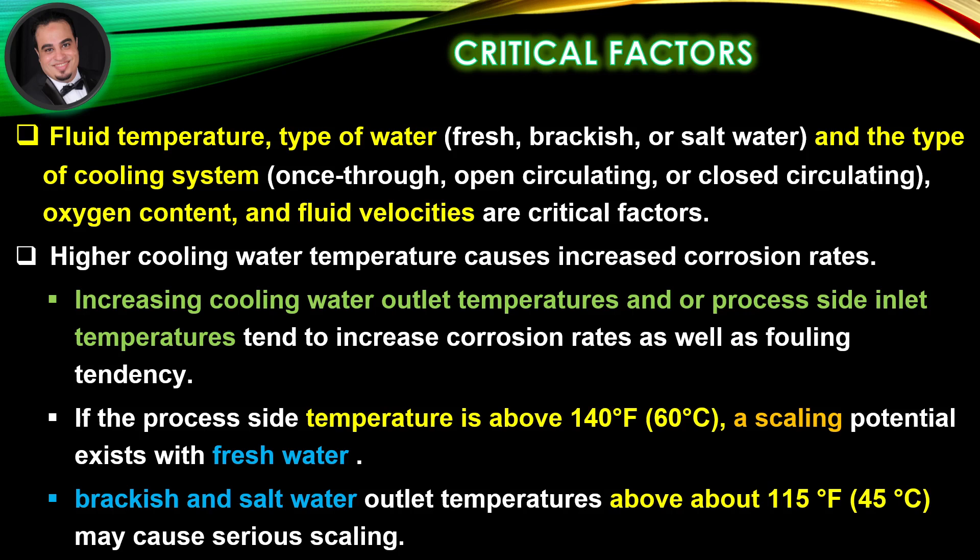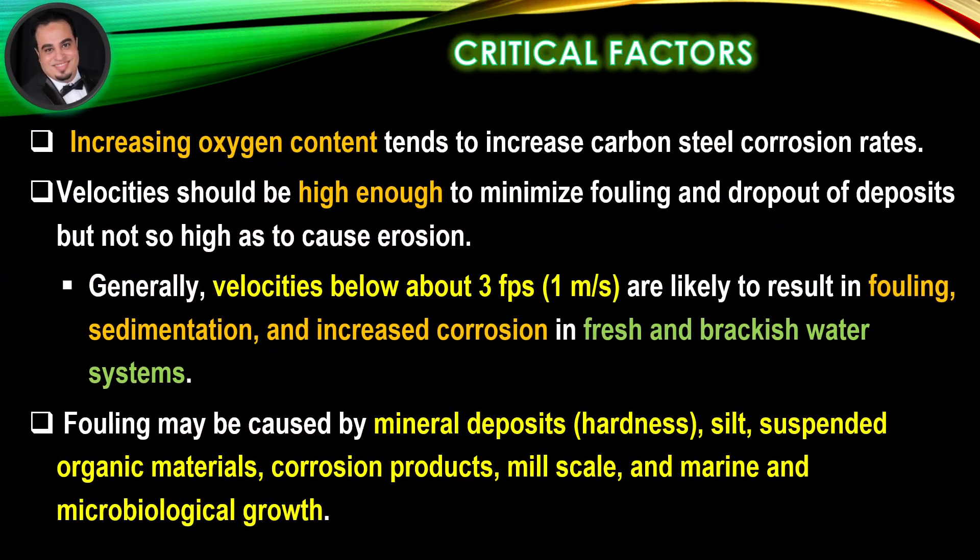With fresh water, brackish and salt water outlet temperatures above about 115 degrees Fahrenheit may cause serious scaling. Increasing oxygen content tends to increase carbon steel corrosion rates.